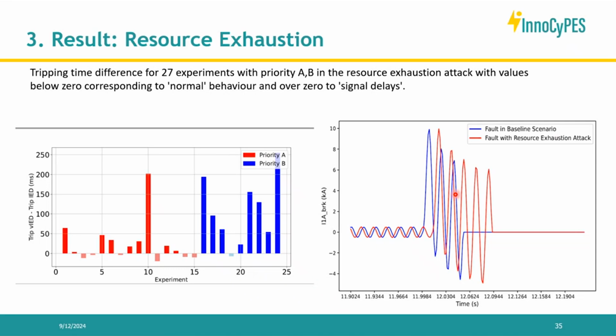And on the power system side, here you can see the impact of the delay in sending the tripping signal. Instead of clearing the fault and the currents going back to zero in just under 10 milliseconds or so, with the delay, it increases the time. You can see that the sinusoidal signal is shifted to the right by a few milliseconds, which people who are more expert in transients can understand the impact of, a few millisecond shift in tripping or opening to clear the fault as well.